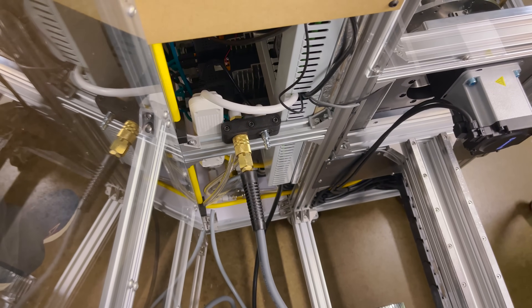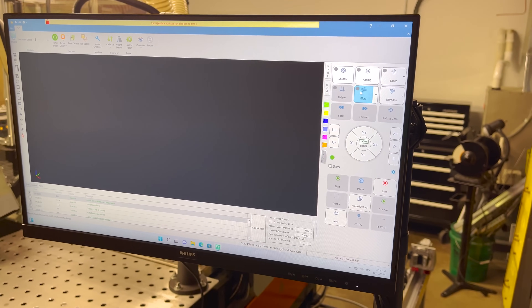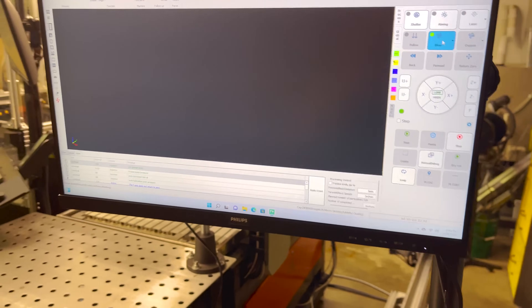I've got my compressed air line plugged in for right now for testing. And when we test the nitrogen, you can hear it blowing. I've switched my air hose over to the oxygen side. It looks like the oxygen regulator is working. I'll go here to global, I'll turn the pressure to like, say 20 psi. You can hear that. Now I'll change it to 120. It looks like the gas system is going to work.